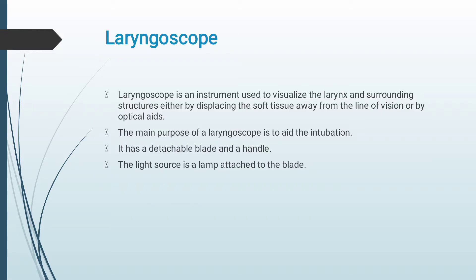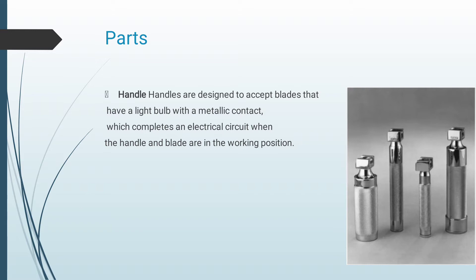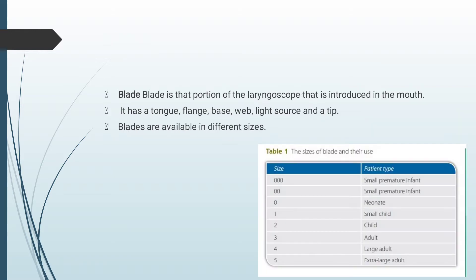Moving on to laryngoscope. A laryngoscope is an instrument used to visualize the larynx and surrounding structures either by displacing the soft tissue away from the line of vision or by optical aids. The main purpose is to aid intubation. It has a detachable blade and a handle. The light source is a lamp attached to the blade. Handles are designed to accept blades that have a light bulb with a metallic contact, which completes an electric circuit when the handle and blade are in working position.